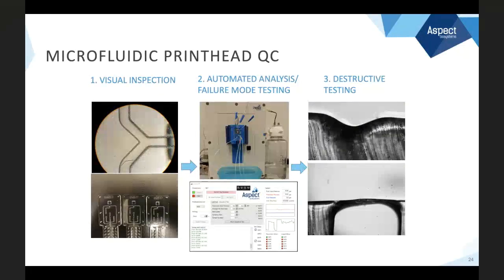We ensure that the valves on these chips are operating at the correct pressures, and then all of this data that we generate during the quality control of the printhead is stored on a microchip that's actually on the printhead. This is an RFID microchip that is able to communicate with the actual 3D printer when the printhead is loaded onto the machine. And what that RFID chip does is it tells the printer exactly what kind of microfluidic printhead it is, so the printer can set itself up in the appropriate way.